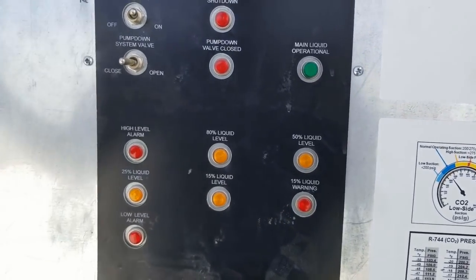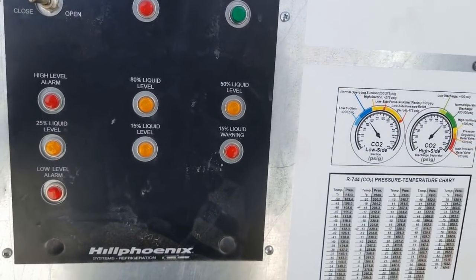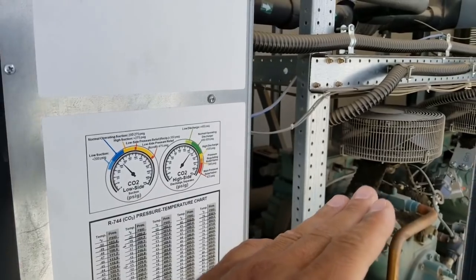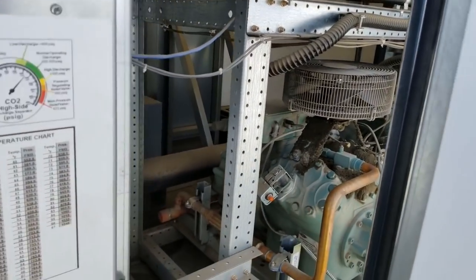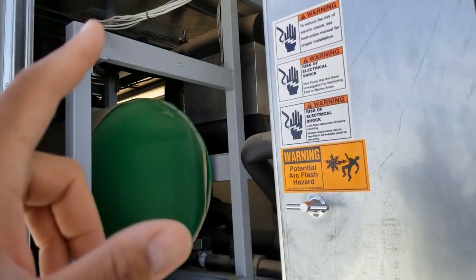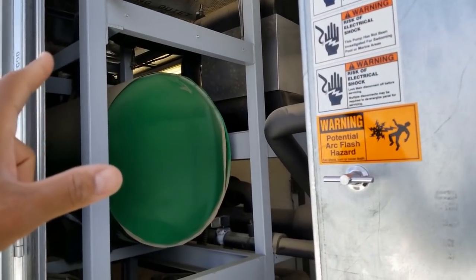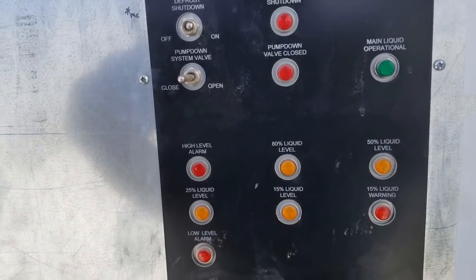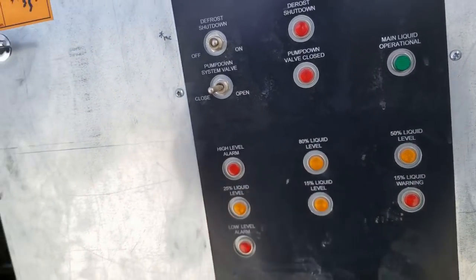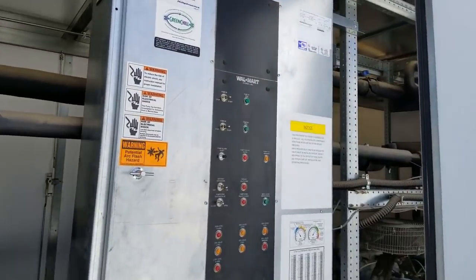So you don't want to automatically start adding CO2 thinking you're low. You want to make sure you get all your compressors running, and all your chillers running before you start adding CO2, because if you start adding it, you can way overcharge the thing, and that's not good. So that's the panel for this.